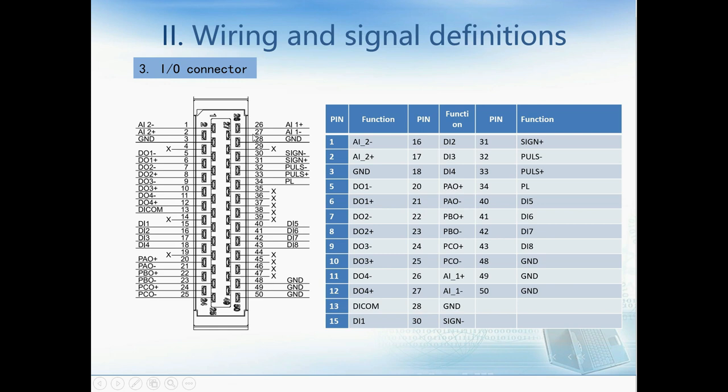Here is the digital output port. This is the signal and pulse port. Generally, these two signals come from the PLC, so we can use the PLC to control the direction and speed of the servo motor. Here is the digital input. And this is PAO, PBO, PCO — the so-called pulse division output. For example, when we input the signal to the servo drive, we can get feedback pulses from PAO, PBO, and PCO.